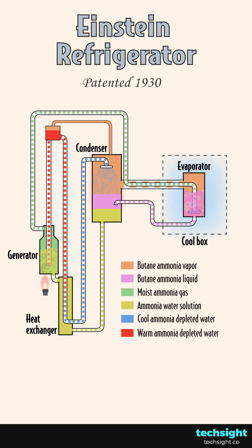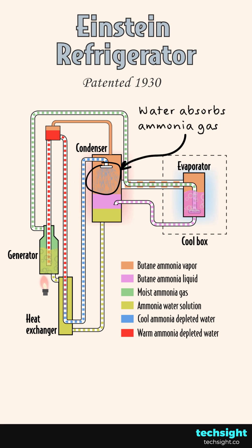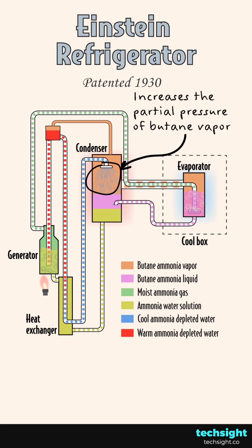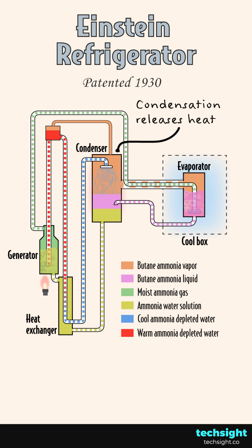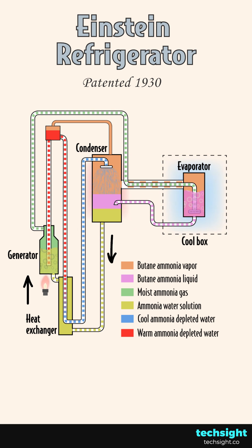But it doesn't stop there. Butane ammonia vapour flows from the evaporator to the condenser. Here, water from the generator absorbs ammonia gas. This increases the partial pressure of the butane vapour in the mixture and causes it to condense into liquid. The condensation process releases the heat picked up at the evaporator. Then the ammonia water solution falls to the bottom of the condenser and returns to the generator to allow the cycle to repeat.